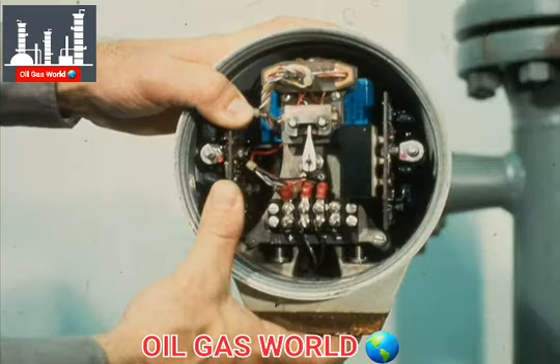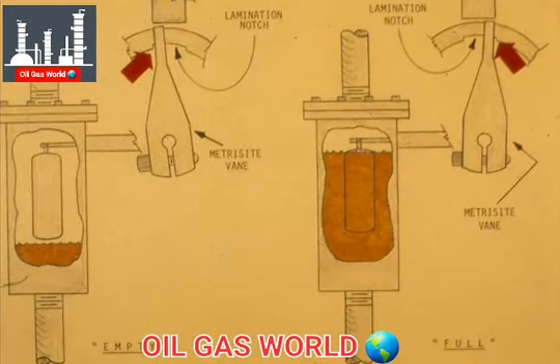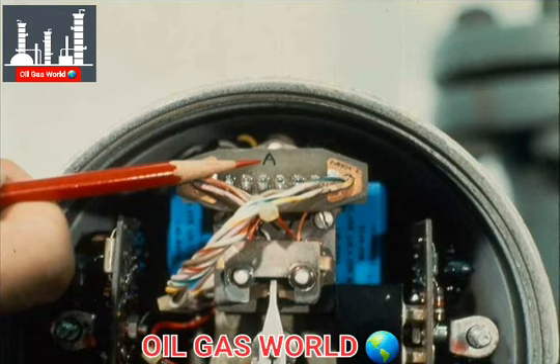Make a visual inspection of the transmitter parts. Make sure the printed circuit boards are plugged in securely. Look for broken or loose wires. Make sure the Metrisite vane is in the proper position relative to the displacer. Make sure the transmitter action is correct.